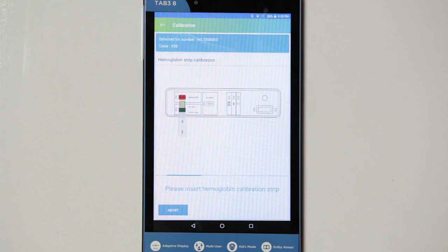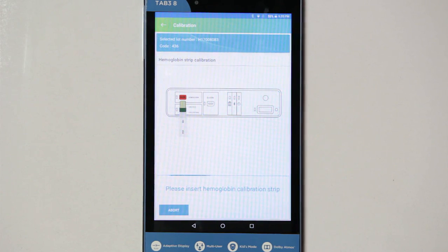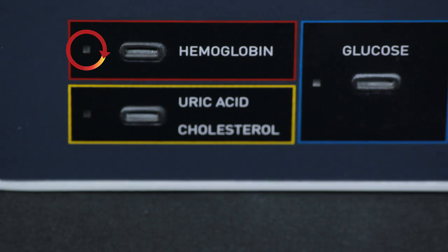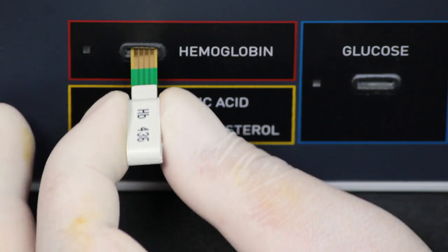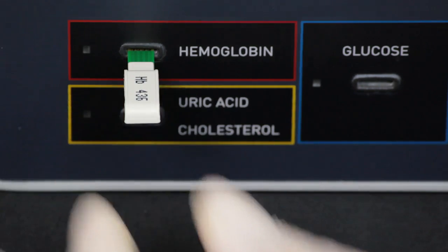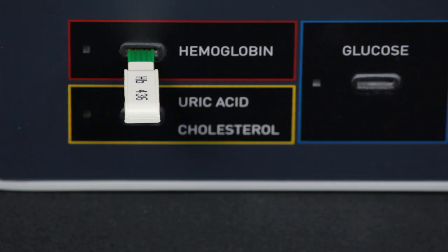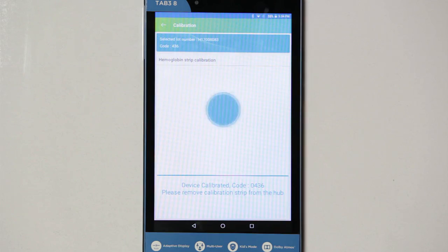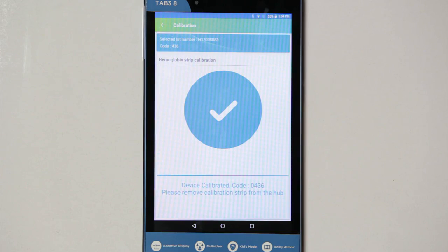This is necessary only every time a fresh pack of strips is used. The LED of the hemoglobin test starts flashing. Insert the calibration strip into the hemoglobin slot of the device. The calibration takes a moment. You hear 2 beeps indicating that calibration is done. The LED goes off. The app shows that calibration is done.